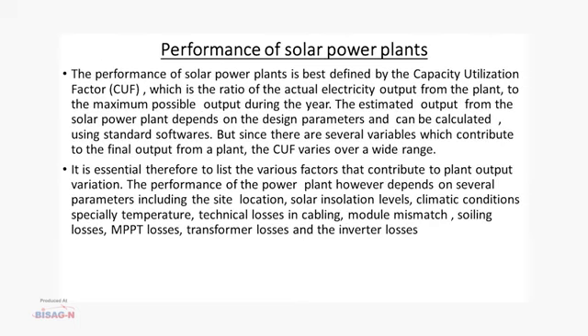Now let us see the performance of solar power plants. The performance of solar power plants is best identified by CUF, that is capacity utilization factor, which is the ratio of actual output from the plant to the maximum possible output during the year. The estimated output from the solar power plant depends on the design parameters and can be calculated using standard software. But since there are several variables which contribute to the final output from a plant, the CUF varies over a wide range.